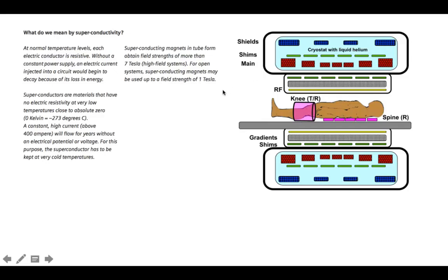It's probably also worth pointing out that the MRI system, because it stays at high current and high field generation even when it's not being actually used, remains a safety issue. So, when entering an MRI room, even if an MRI is not actively being used to acquire data, one should always be aware that this magnetic field is there, that the main magnet is active, and so appropriate safety precautions should be taken. What are those?